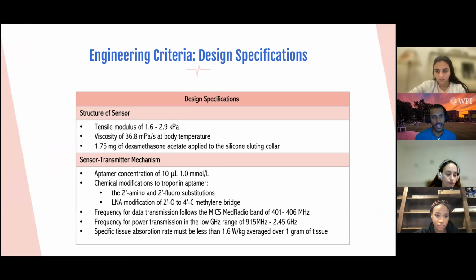From studies about the mechanical characteristics of subcutaneous tissue, it is shown that the tensile modulus ranges from 1.6 to 2.9 kilopascals, while the viscosity of the interstitial fluid in the tissue is 36.8 millipascal seconds at body temperature. In terms of design specification, the PMMA casing of the biosensor must be able to integrate well with the subcutaneous tissue located near this region, therefore must be properly designed with these values in mind. For reducing inflammatory response, 1.75 milligrams of dexamethasone acetate will be applied to the eluting silicone collar surrounding the sensor. Previous studies done by Eversense showed that this specific dosage was ideal for the most effective anti-inflammatory response.